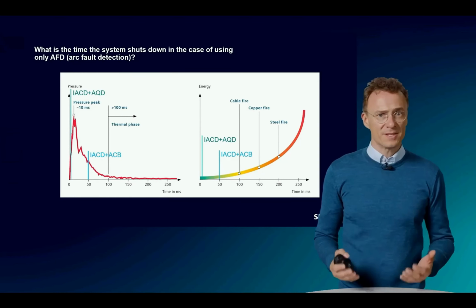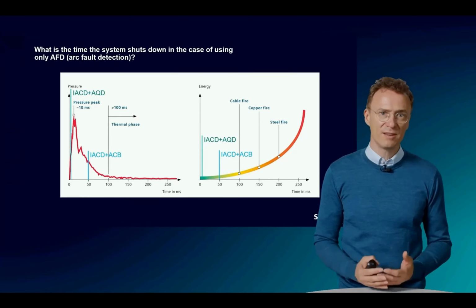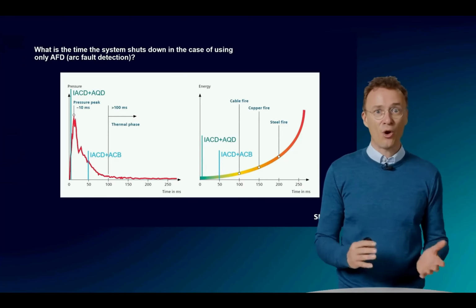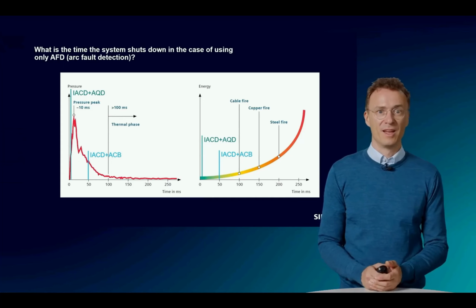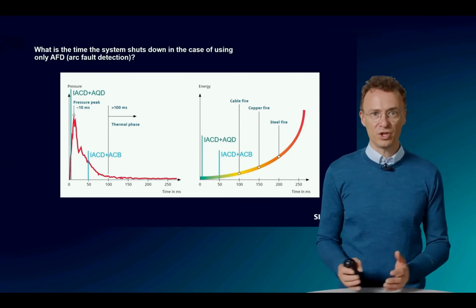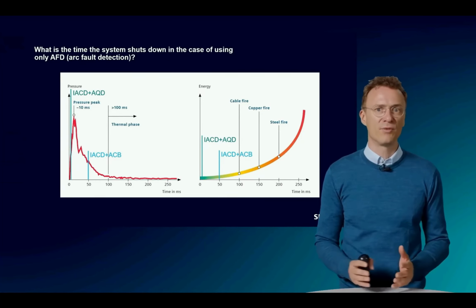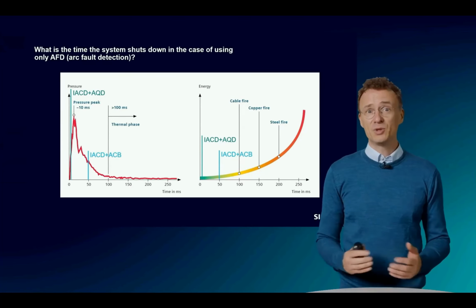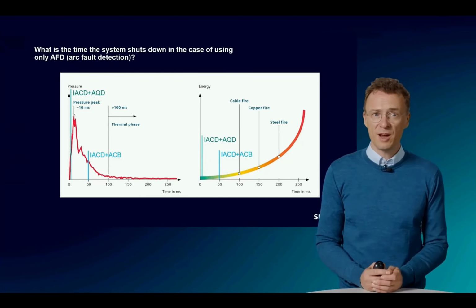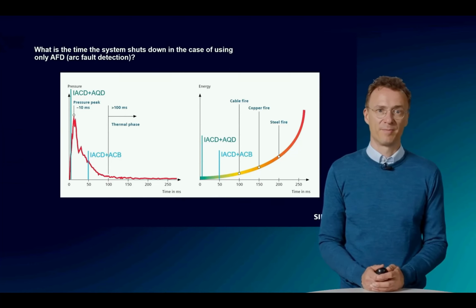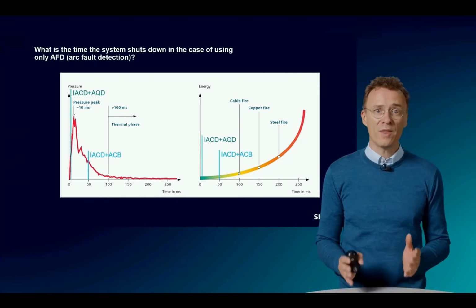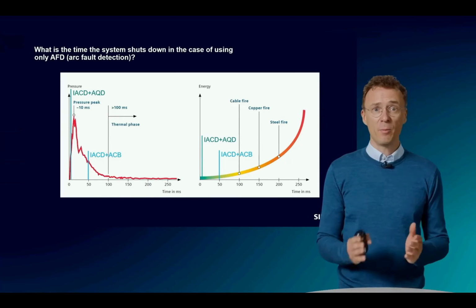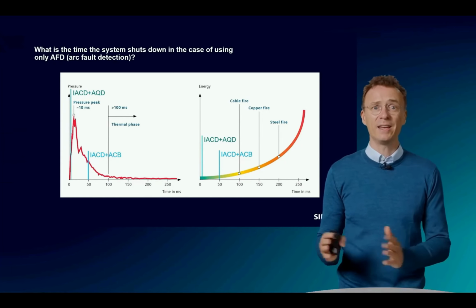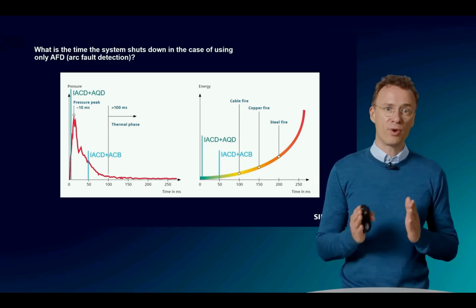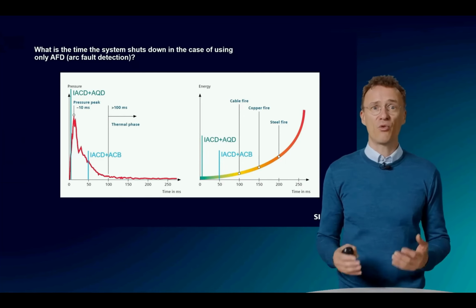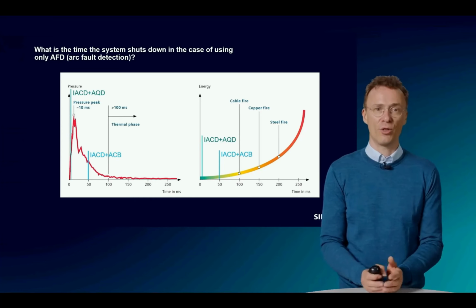What is the time the system shuts down in case of only using IACD or arc fault detection? Using only the detection without the quenching device, the tripping time is approximately 50 milliseconds. Using the AQD reduces the tripping time to below 5 milliseconds. And in the graph, you can see why this is important. Using a combination of IACD and AQD gets you even ahead of the pressure peak. And this really minimizes the mechanical stress on the system.